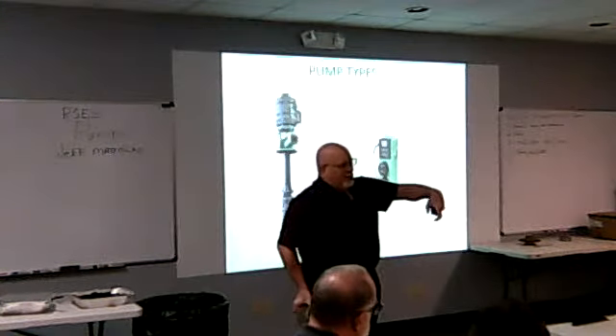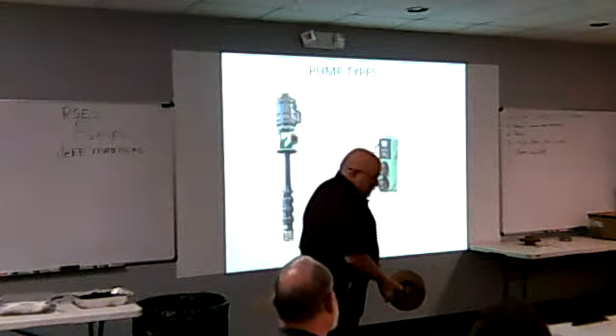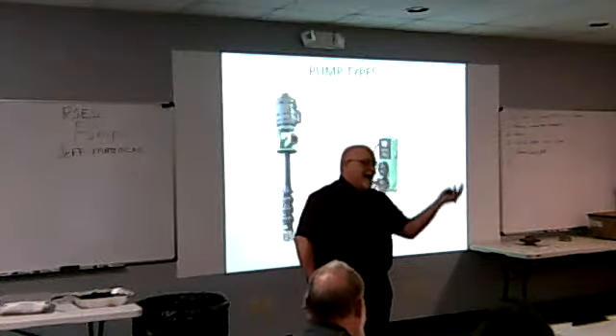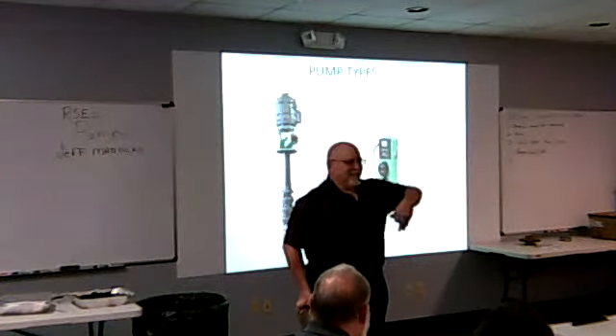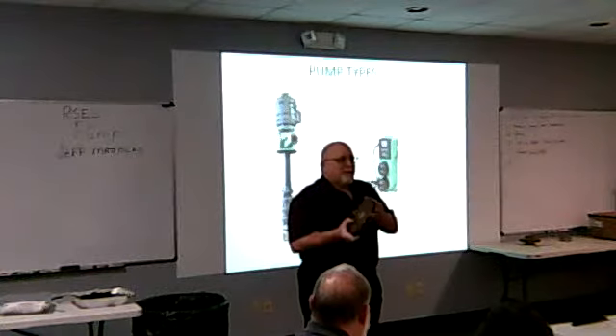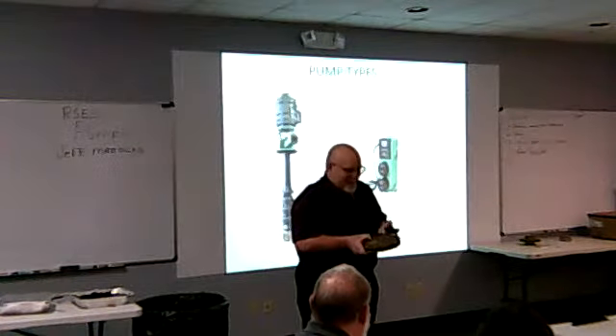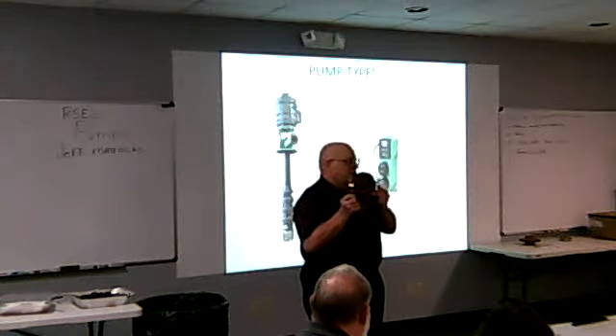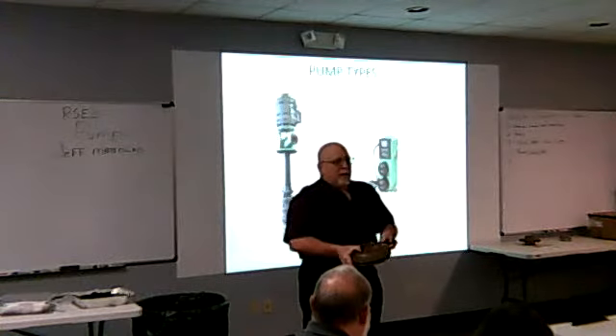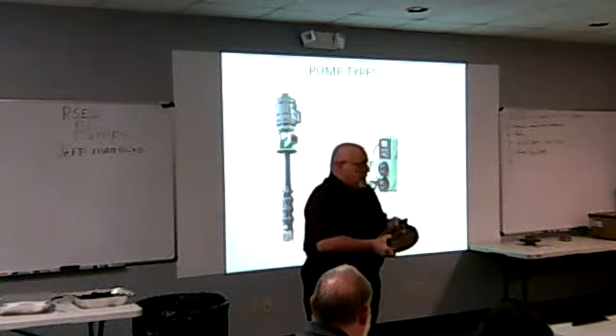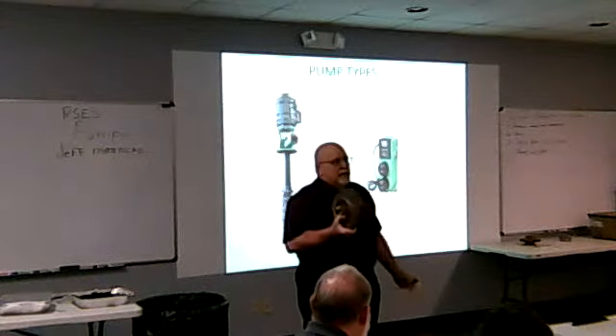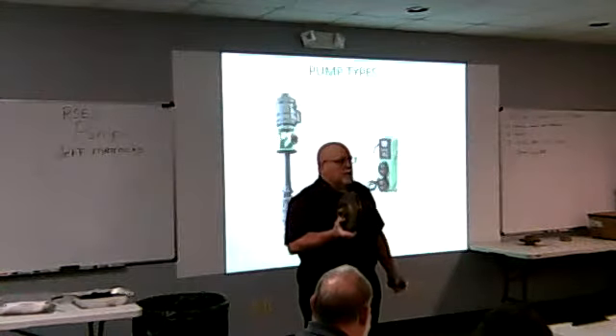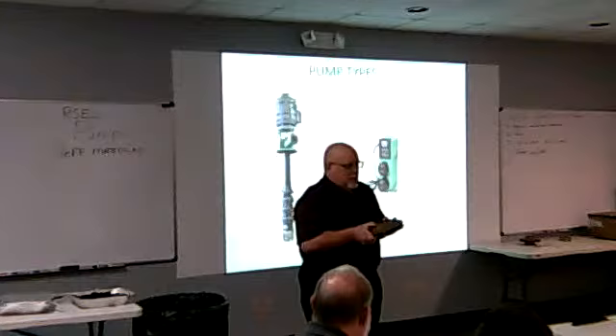You don't want to bite into the water. You ever have to figure out the rotation? You want to backhand it, not bite in. They're not cups that throw water down the pipe. Exactly. And these are trimmed. It says 8.8. We can trim impellers. So I'll get into that in a minute. These are typically bronze, can be stainless, iron. There's all sorts of different applications.